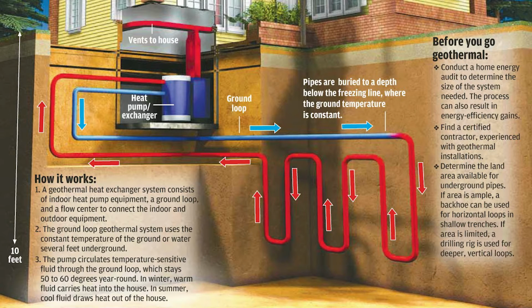Then you have a ground loop, either closed loop or open loop. This slide shows a closed loop system where water circulates through a set of pipes, probably made of polyethylene or polybutylene, underneath the ground. In this application, we had an open loop system pumping out of a well and dumping back into the well. So you have a flow center, which is your pump, and that circulates the water through the pipes connecting the indoor and outdoor equipment.